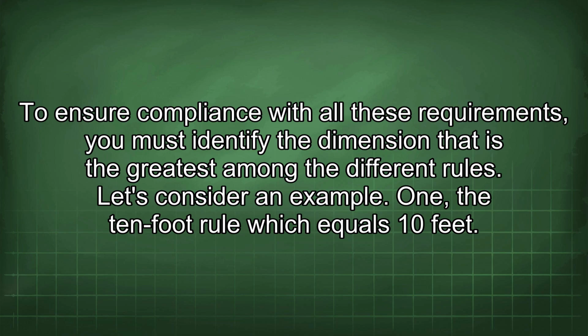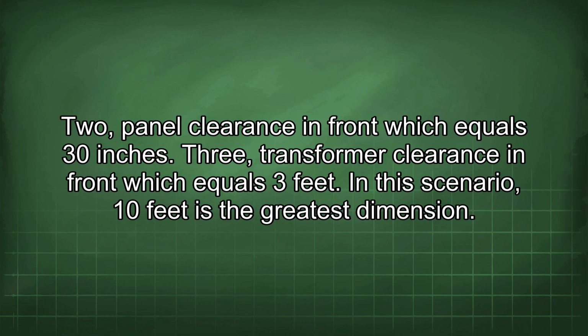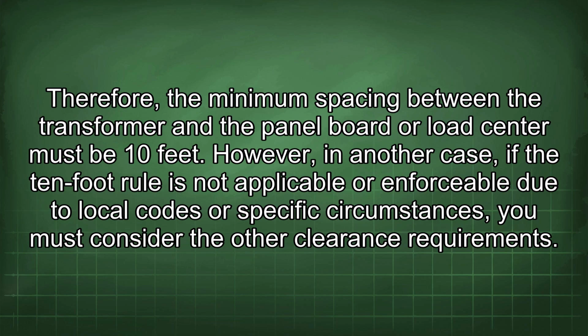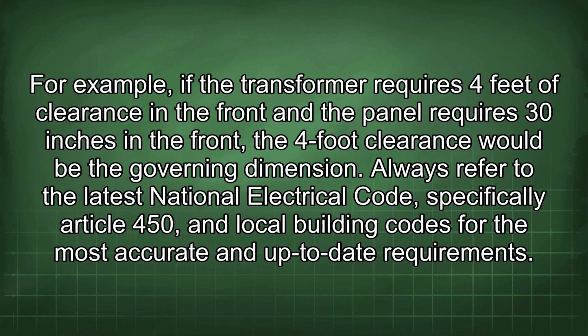Let's consider an example. 1. The 10-foot rule, which equals 10 feet. 2. Panel clearance in front, which equals 30 inches. 3. Transformer clearance in front, which equals 3 feet. In this scenario, 10 feet is the greatest dimension. Therefore, the minimum spacing between the transformer and the panel board or load center must be 10 feet. However, in another case, if the 10-foot rule is not applicable or enforceable due to local codes or specific circumstances, you must consider the other clearance requirements. For example, if the transformer requires 4 feet of clearance in the front and the panel requires 30 inches in the front, the 4-foot clearance would be the governing dimension.